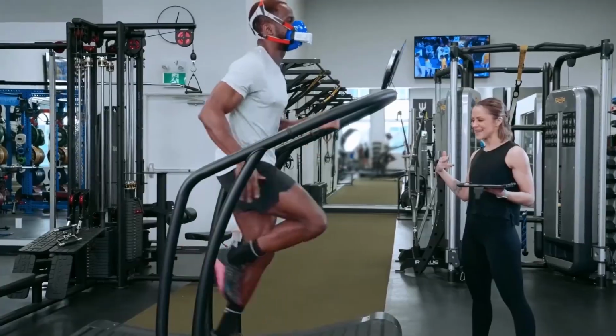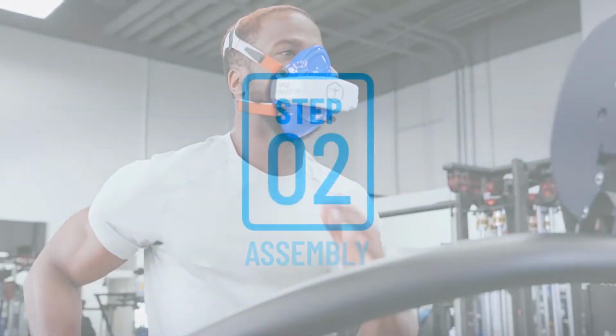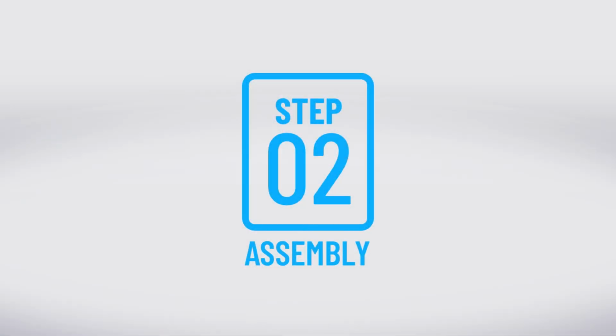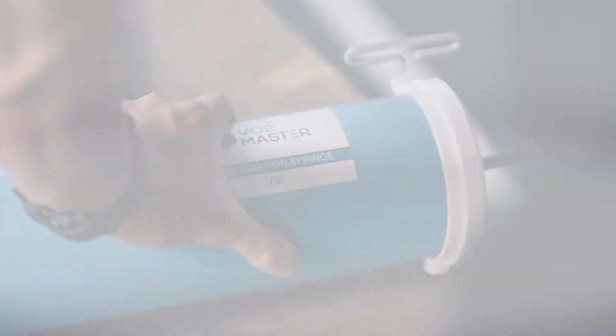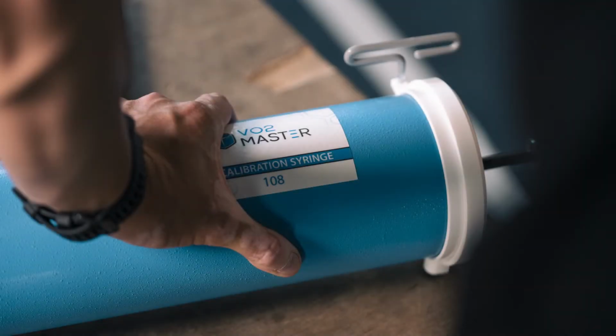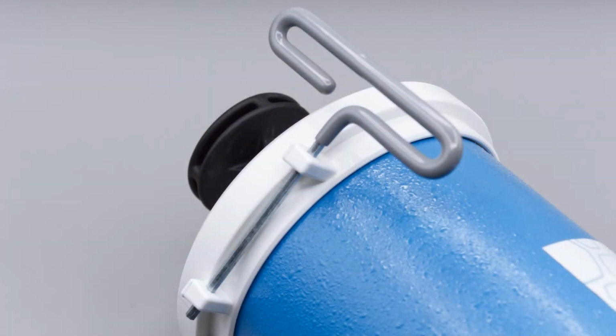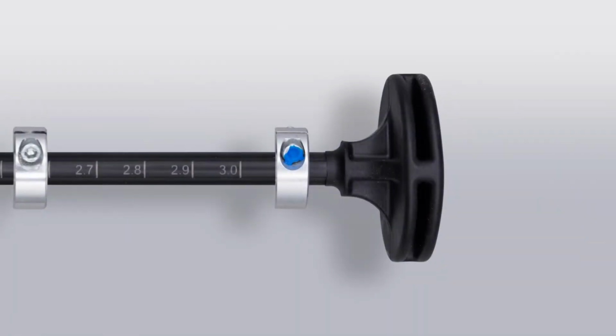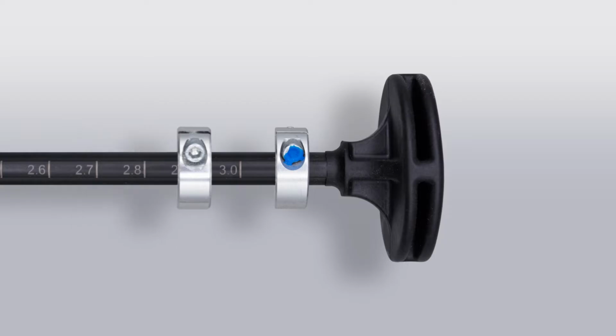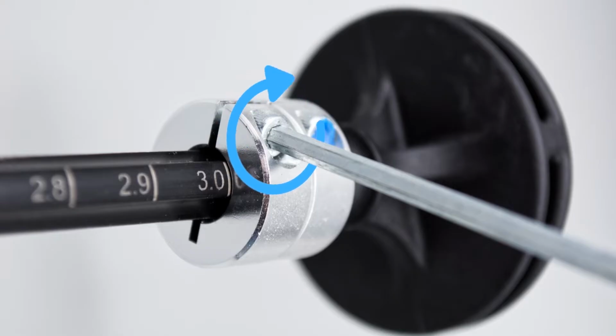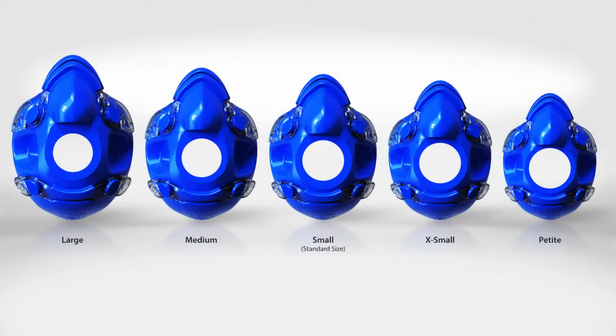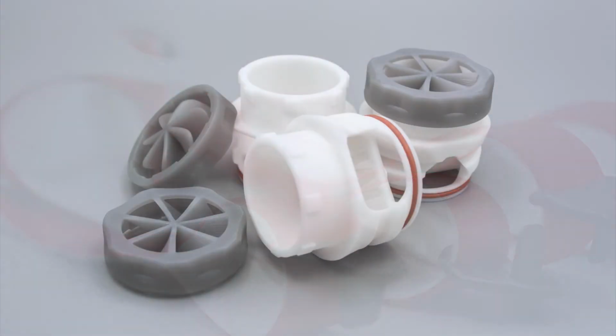For the duration of this episode, we will be referencing the performance test in our examples. Now that we have chosen a test type, we can begin with Step 2, Assembly. We will start by ensuring the calibration syringe is set to the correct volume of 3.0 liters based on our chosen test type. If you are required to set your syringe volume, use the provided hex key to loosen the lock collar just enough to freely slide it along the plunger arm until it reaches the correct volume position, then secure it into place. We will now select the appropriate mask size, matching headgear, and user piece for our chosen test type and test subject or athlete.